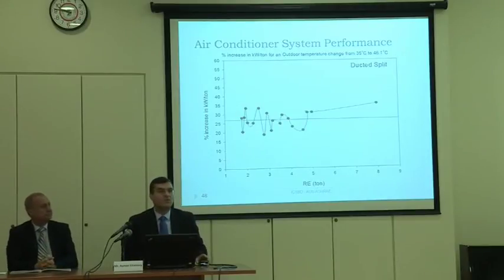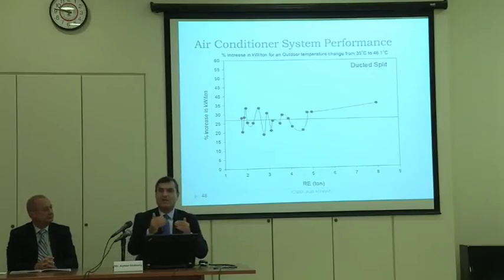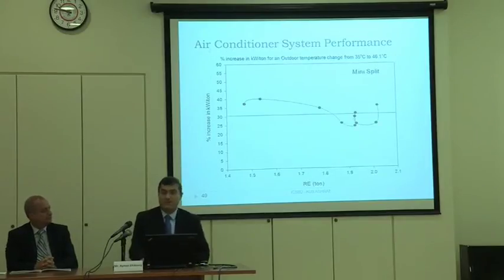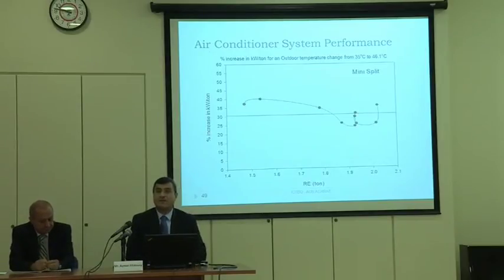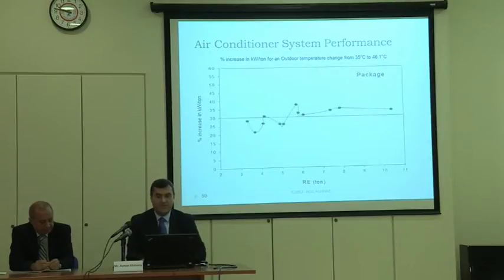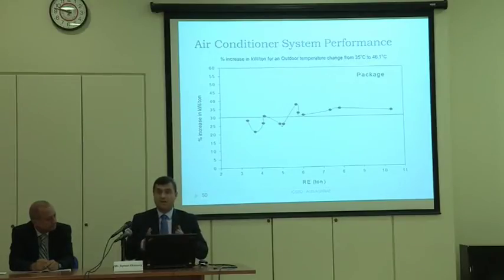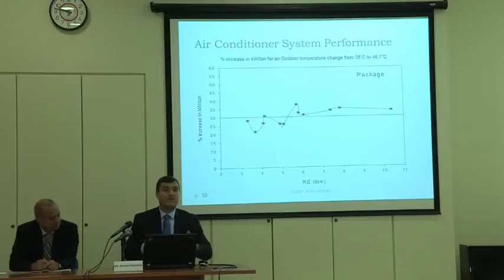Meaning, if I have to make a conclusion out of this, the design by the manufacturer does not really make much difference between, for example, machine A, machine B, machine C by different companies. They're all losing the same range of efficiency. But the mini split also has an efficiency loss of 30%, for example. There are variations from one machine to another. If I go to package, there is also some loss of efficiency, about 30%, meaning EER values can go down as high as 30% from 35 to 46.